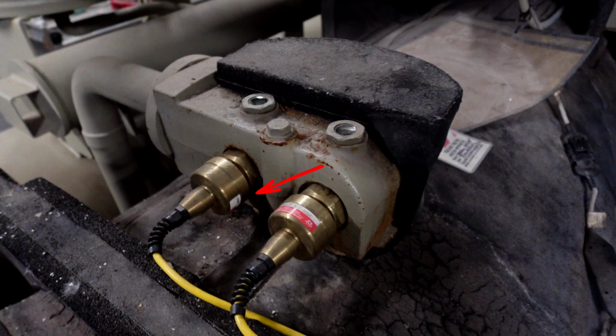So my point is you'll start to see these EXV blocks scale up into larger systems, but there is a breakover point to where you either have to go with a really large valve, which financially may just not make sense, or you have to start splitting these valves up into a multi head function like this in order to get the same volume and flow. Any questions so far up to this point on these valve bodies?